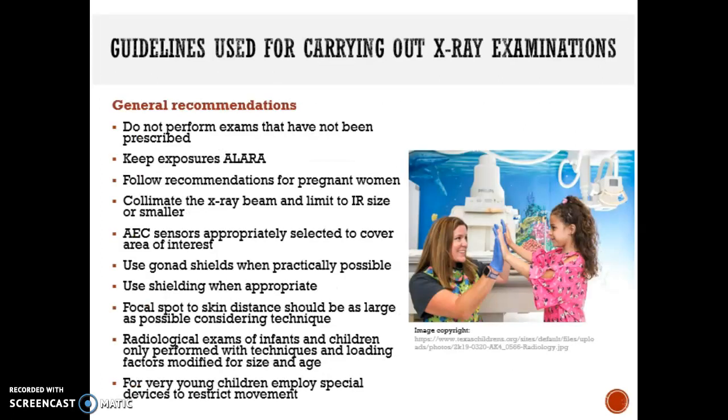The key points to remember when carrying out X-ray examinations, and this is based on Canada's Safety Code 35, is do not perform exams if they've not been prescribed by a doctor. Always keep those exposures as low as reasonably achievable and follow the recommendations, especially when it comes to pregnant women, because you don't want to cause unnecessary dose to the fetus. Always collimate the X-ray beam and limit the collimation field to the size of the image receptor or smaller if that's possible. Use automatic exposure controls when it's possible.